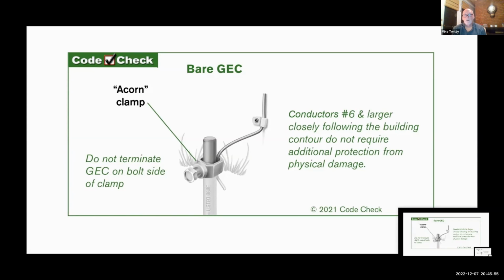Conductors number 6 and larger, if they closely follow the building contour, don't need additional protection from physical damage. Weed eaters are terrible on these things. People beat them up. You wouldn't think over time that the nylon cord would cause damage, but over time it can beat them up, loosen them up. So they should be protected when they're exposed to physical damage.